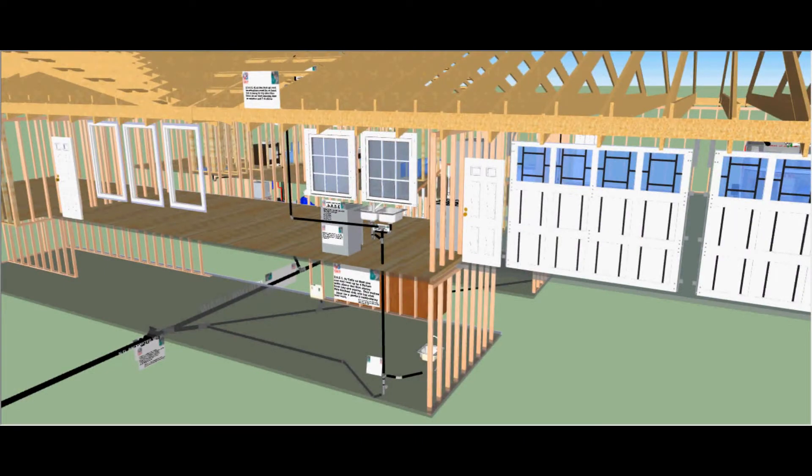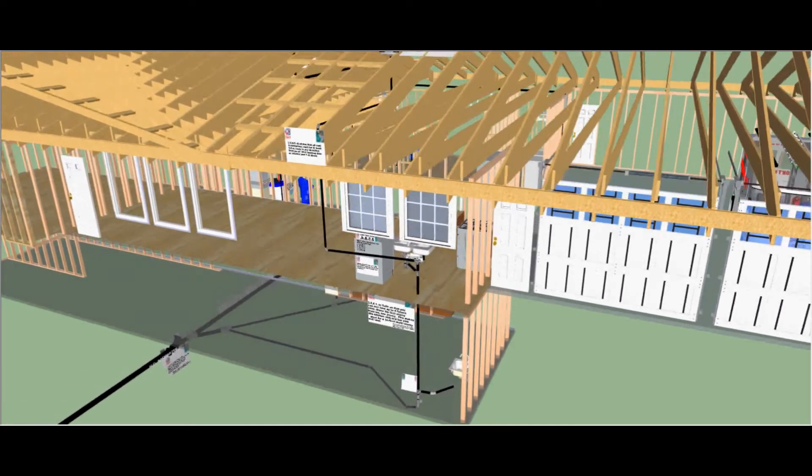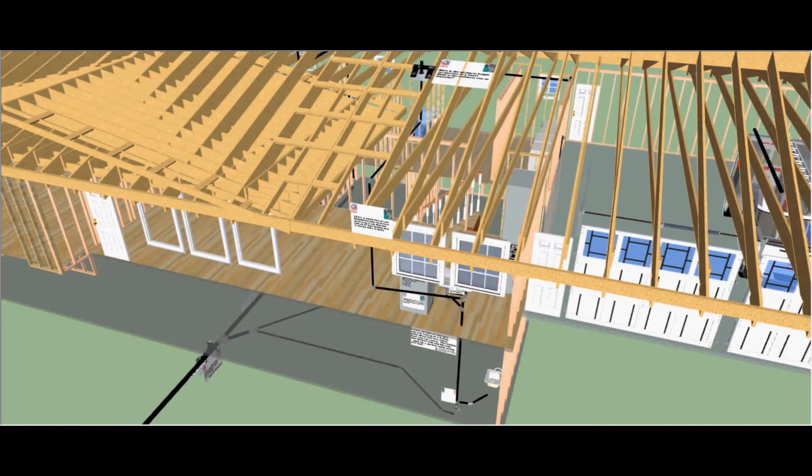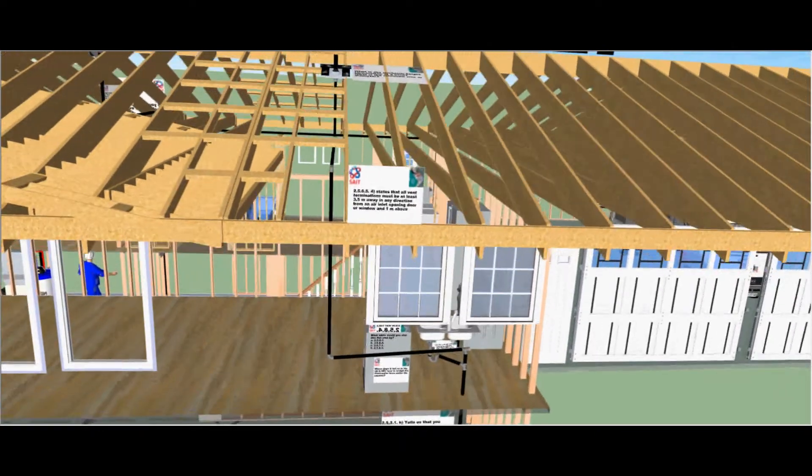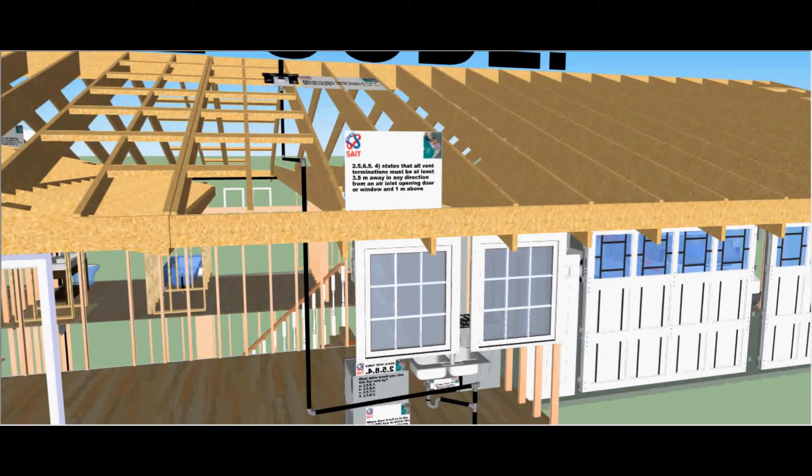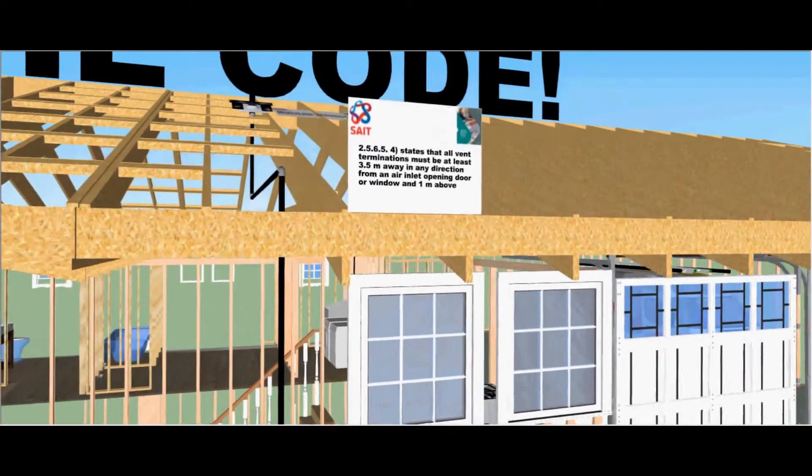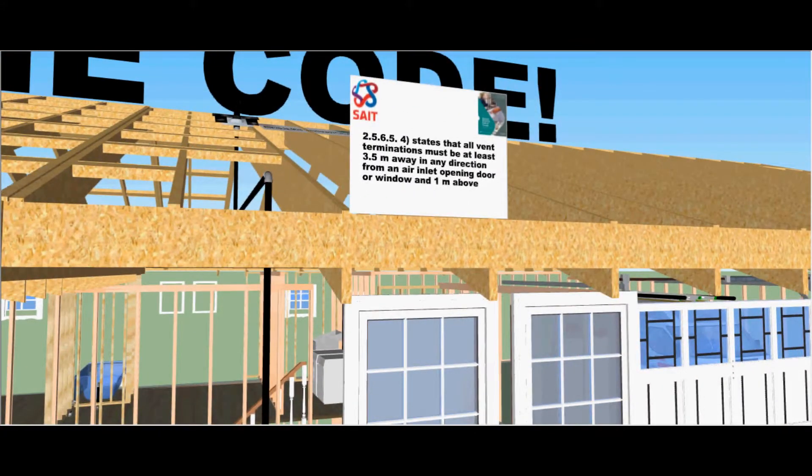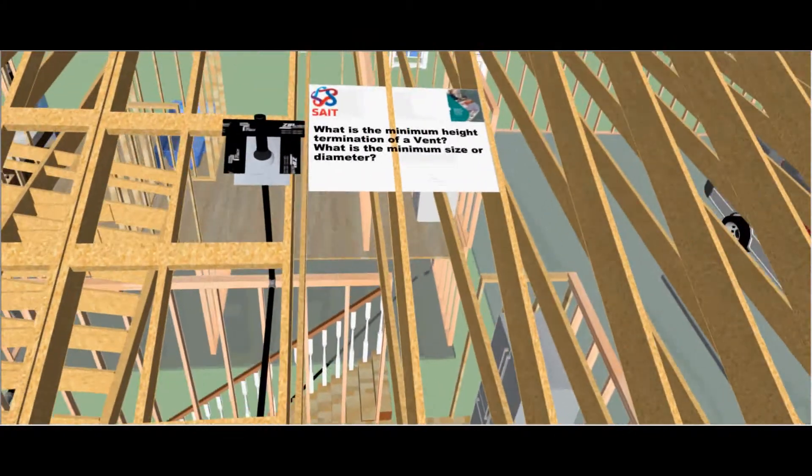Now let's take a look at the venting system. Here we see we have two windows above the kitchen so we had to run a flat vent. In the code it states that all vent terminations must be at least three and a half meters away in any direction from any air inlet opening, door, or opening window, and one meter above.